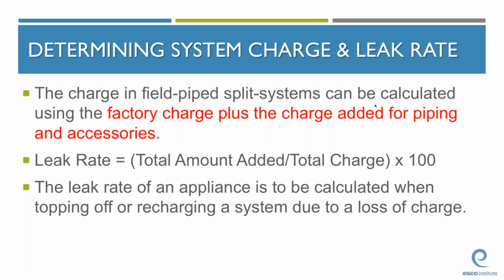Now, it should be noted that the total amount of refrigerant is ideally the amount of refrigerant added over a 12-month period, but you don't have to wait 12 months to calculate that. So, for example, if a system is repaired at the beginning of February and a technician adds 100 pounds of refrigerant to that system, and then at the end of March, an additional 100 pounds of refrigerant has to be added to that system, we added 100 pounds of refrigerant over 2 months. So by extrapolating, that would actually come out to be a leak rate of 100 pounds of refrigerant every 2 months for 1 year, giving us 600 pounds. So that can actually be extrapolated out as well. Now, depending on the total charge of the system, we can determine the actual percentage of the leak rate.